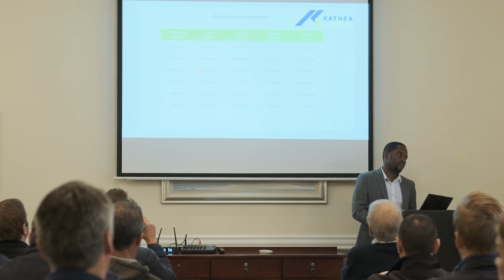start working. So when you don't see any of those LEDs on, you should not worry. Your inverter could be in initialization mode or it could be on standby. Then none of those lights will be on. To save power, even on those LEDs, if the inverter is not producing anything and it's just idle, they switch off. But the moment you start drawing anything from it, the EPS light will be on to show that it's producing. Then the grid light will be on when you've got grid, and the rest will be off. When you are on off grid, it's only the EPS light that is on, the rest will be off.